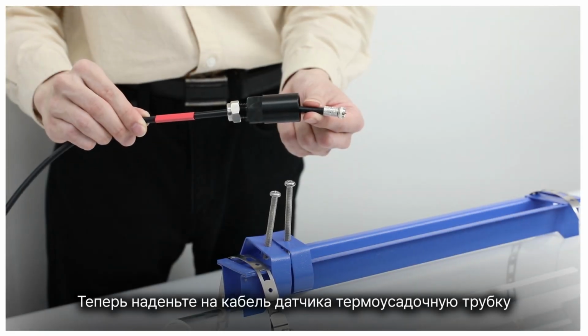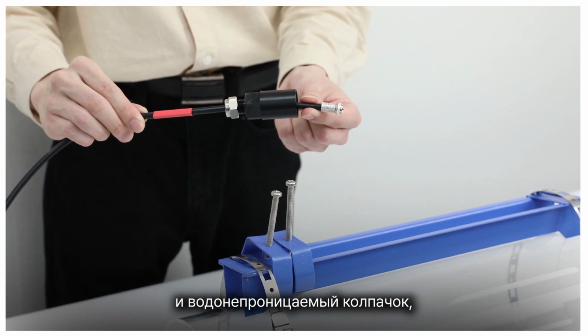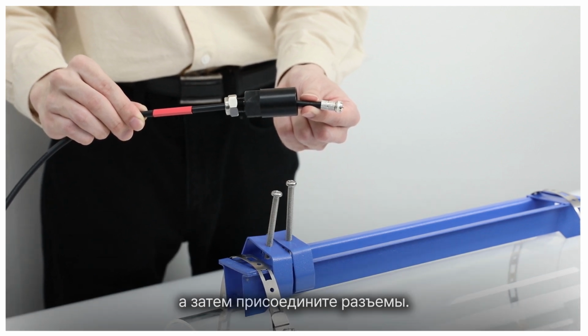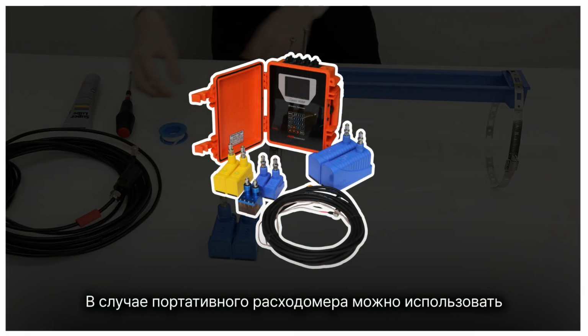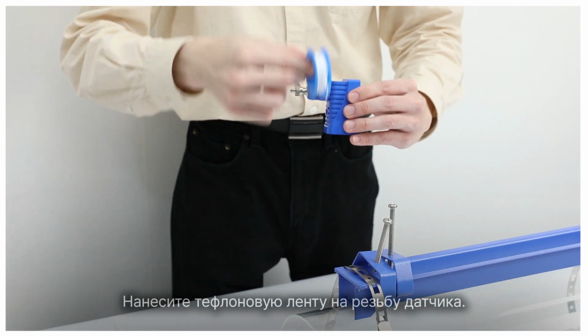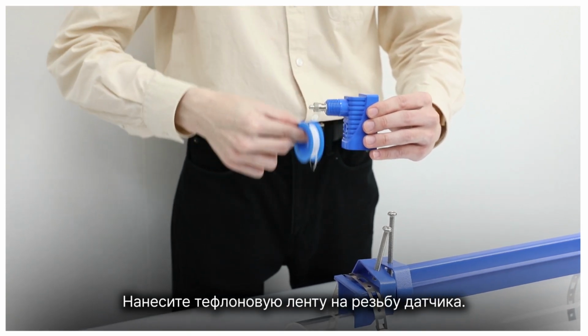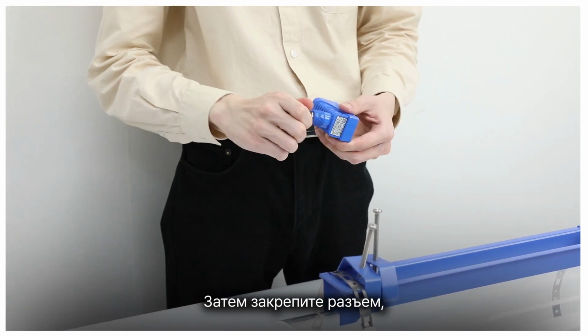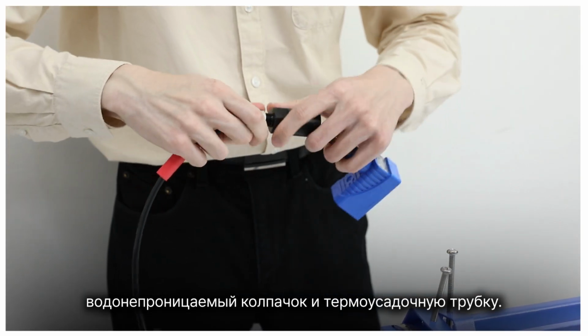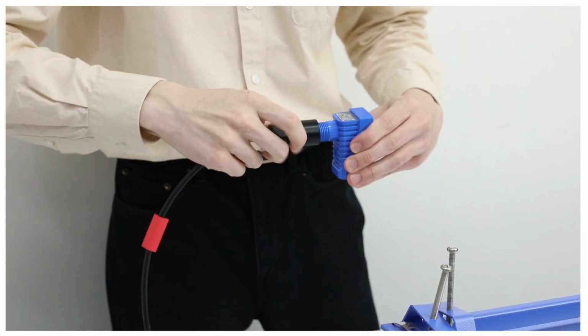Now put a shrink tube and waterproof cap on the sensor cable and then attach the connectors. In the case of a portable flow meter, you can use the cable as provided. Apply Teflon tape to the transducer's threads, then fasten the connector, waterproof cap, and shrink tube.